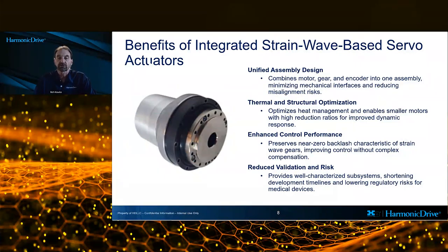Benefits of integrated strain wave-based servo actuators. Integrated servo actuators built around strain wave gear technology offer several advantages that directly address the design challenges of medical systems. By combining the motor, gear reduction, and encoder into a unified assembly, these actuators reduce the number of mechanical interfaces where misalignment, tolerance stack-up, or assembly errors can occur. This integration improves repeatability and simplifies system-level reliability analysis.